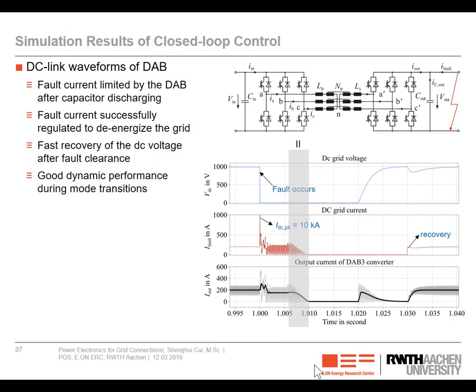And when the DC current is fully nullified, then even a mechanical disconnector can easily open and isolate the fault. Here, the fault is isolated, and afterwards, this DC-DC converter injects a certain current into the capacitors to rebuild the DC grid voltage. And as soon as the DC grid voltage is restored, the grid can operate normally once more. And currently, we are building a downscale prototype, and I think we will see the experimental results soon.